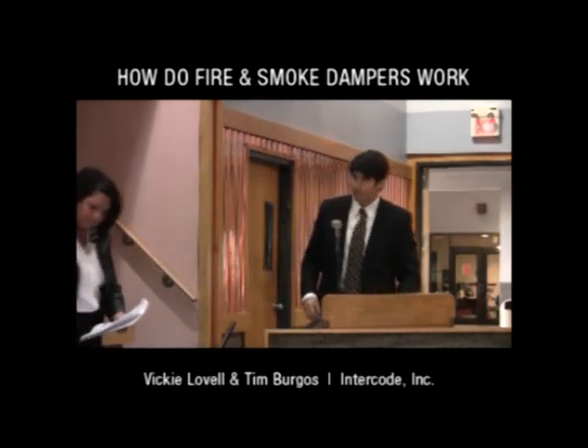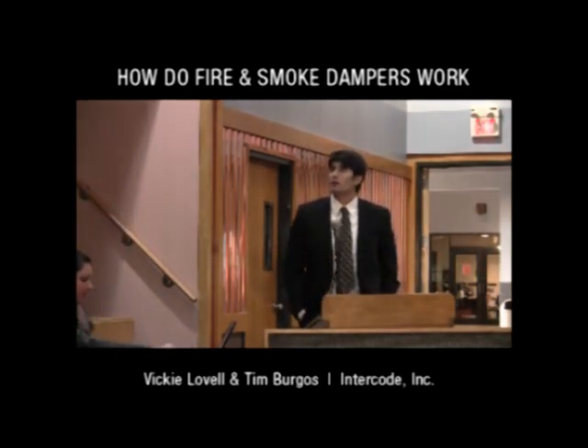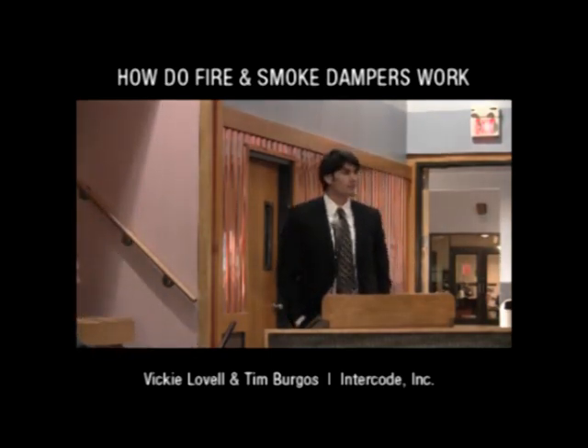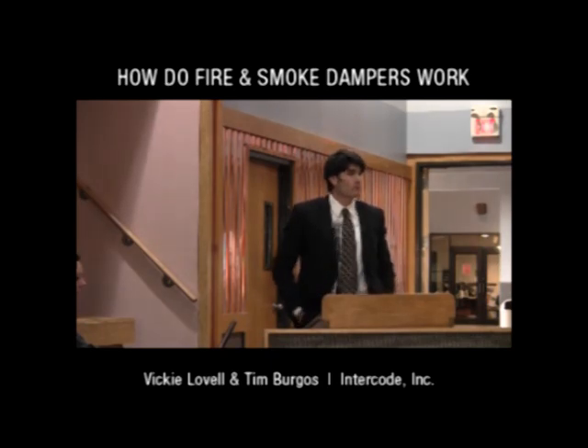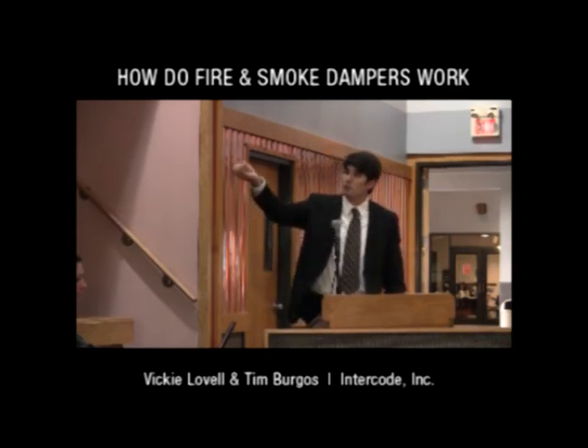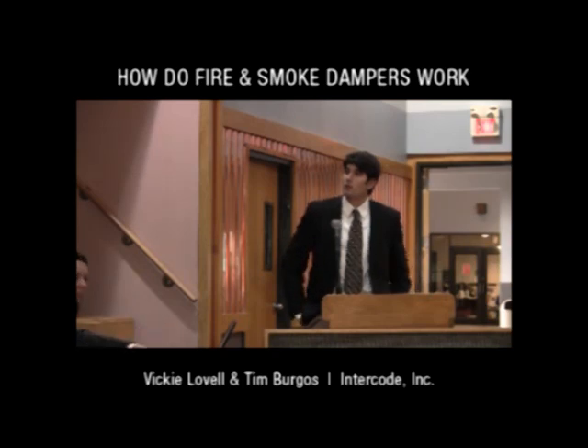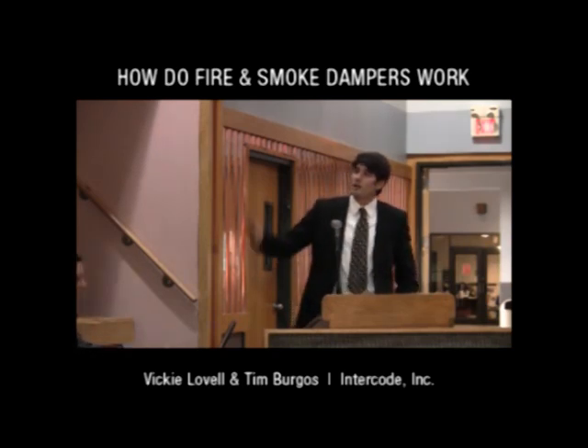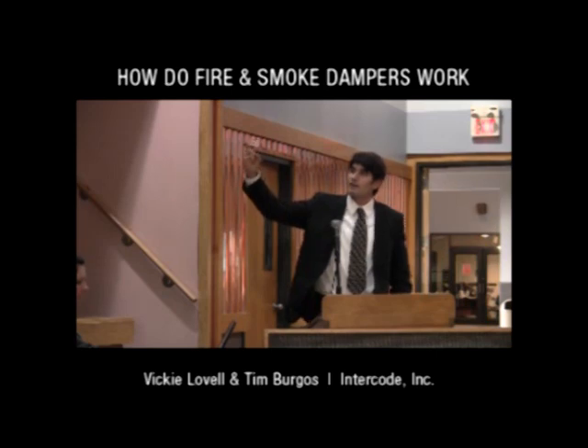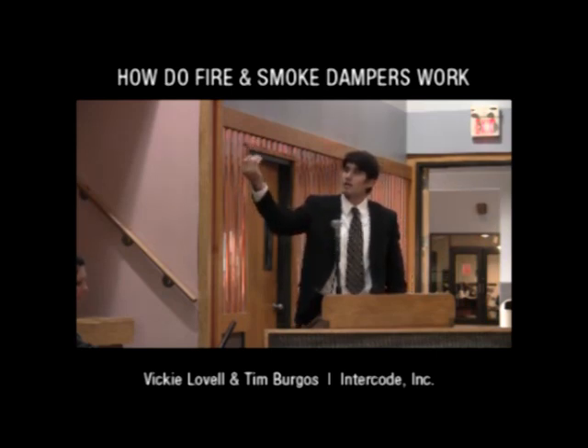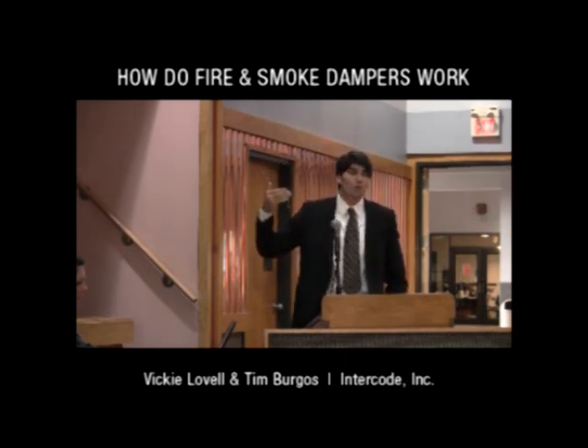Hello, everyone. We already briefly talked about a damper, but I'm just going to go into a little more detail about what a damper does and the function of a damper. A damper helps resist the spread of flame and smoke throughout the HVAC system, and also helps to maintain the hourly rating of a fire assembly. As you see in this picture, it shows you what a damper will do. There's a fire on one side of this wall, and that's a fire-rated wall, and then the damper is located inside this HVAC duct. So instead of the flame and smoke spreading through the HVAC system, it's blocked by the damper, so people on the other side of that wall won't be affected by the fire.